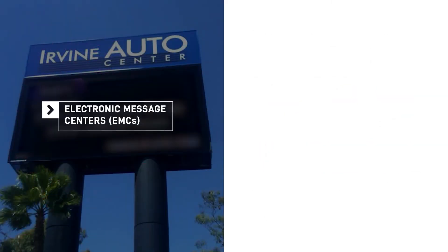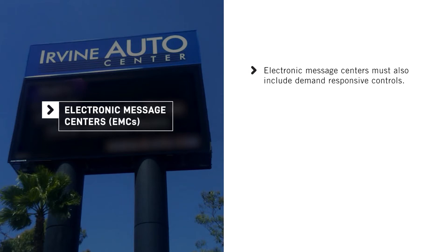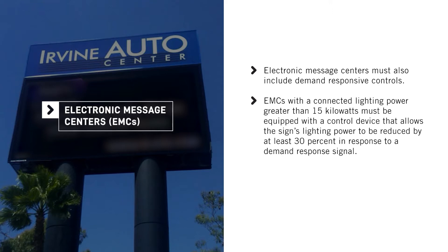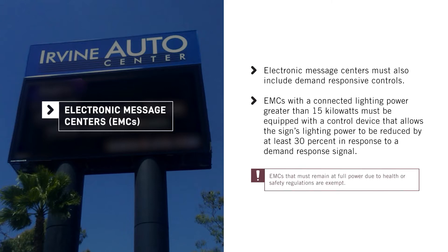A specific type of outdoor sign called an electronic message center, or EMC, must also include demand responsive controls. EMCs with a connected lighting power greater than 15 kilowatts must be equipped with a control device that allows the sign's lighting power to be reduced by at least 30% in response to a demand response signal. EMCs that must remain at full power due to health or safety regulations are exempt.